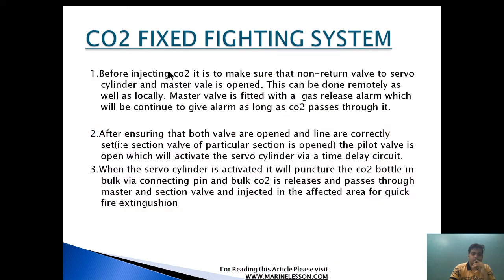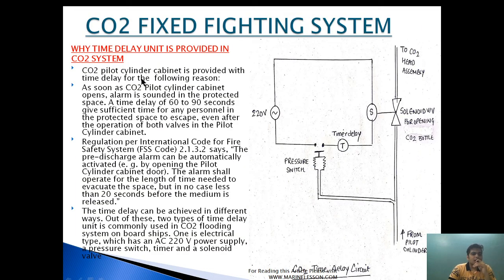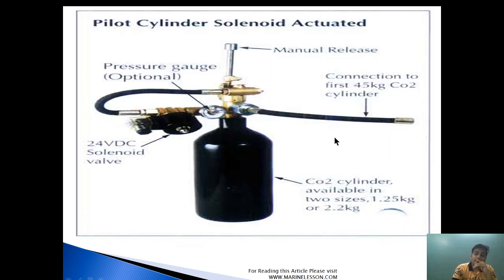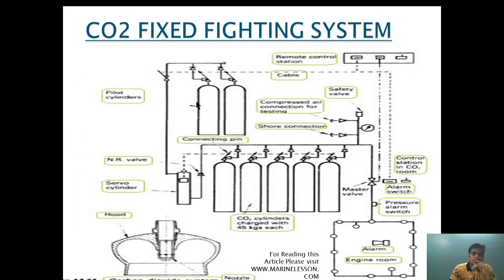The CO2 pilot cylinder cabinet is provided with a time delay for the following reason: as soon as the CO2 pilot cylinder cabinet is opened, an alarm sounds in the protected space, which is the engine room. A time delay of 60 to 90 seconds gives sufficient time for any personnel in the protected space to escape, even after the operation of both valves in the pilot cylinder cabinet.